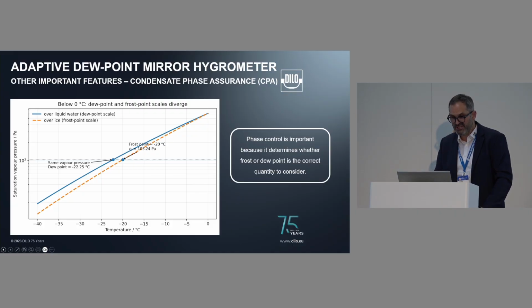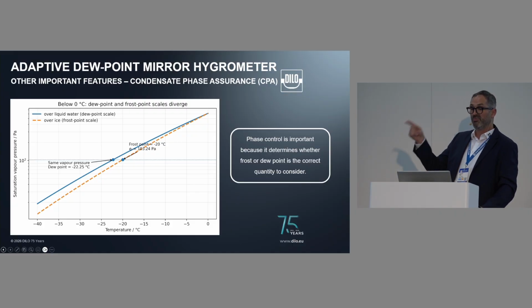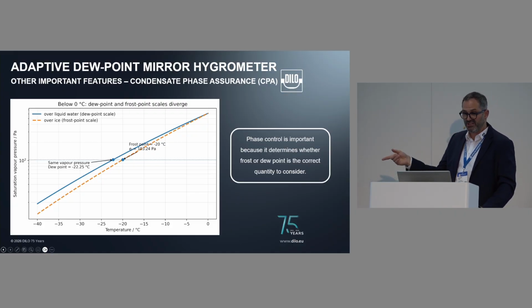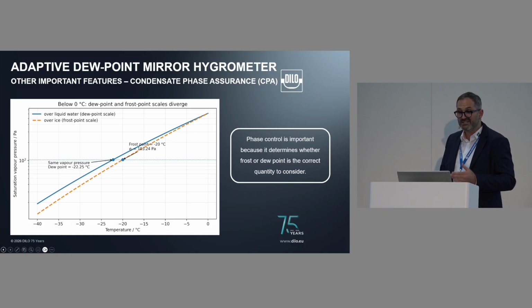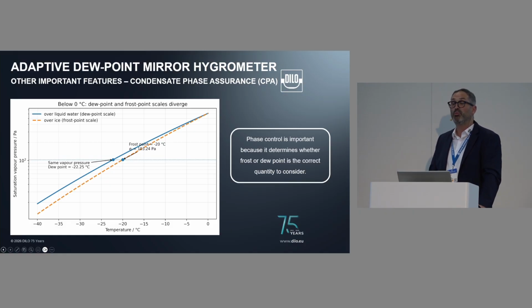And this means if you sync your mirror, it measures at minus 20, but it should measure ice. But in reality, it's rather the dew point that is correct at that point. You make a difference, you make an error of, let's say, in this case, 2.25 degrees Celsius. And no matter how good your instrument accuracy is, the error is quite huge.